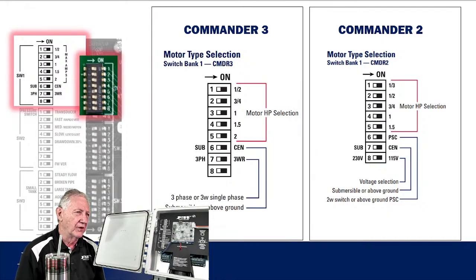Now that's really true for those horsepowers that you see listed above. When you get to position 6, you've got a choice to make. If you want this to be a submersible pump, you need that 6 to be in the left-hand position, where it's at now. If it's a centrifugal motor, you're going to switch that over to the right-hand position. Basically what we're talking about is an above-ground motor. This drive will run above-ground motors, even the permanent split capacitor.